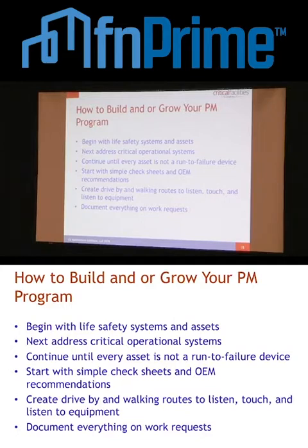The key is if you have the data, you can determine all this stuff and outsmart it. Well, the book says change every 12 months. Well, you don't need to do that. I did a data center on the West Coast, and the OEM said you change the filters once a quarter. So I go down to visit, and those of you on the West Coast, I'd never seen them on the East Coast, but the cattle finishing yards right before they go to slaughter, thousands and thousands of cows, was next door to the building.